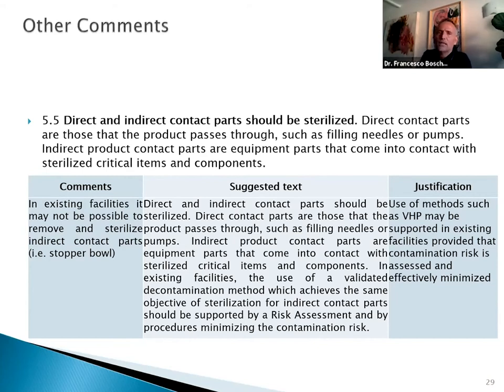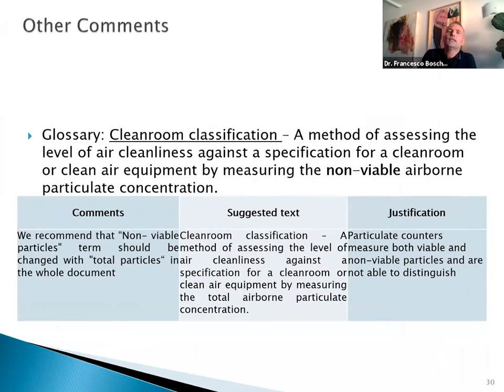What we suggest is that for existing facilities, the statement should allow that the use of a validated decontamination method which achieves the same objective as sterilization for indirect contact parts should be supported by a risk assessment and by procedures minimizing the contamination risk. We adopted the same wording as the annex uses for the RABS class.